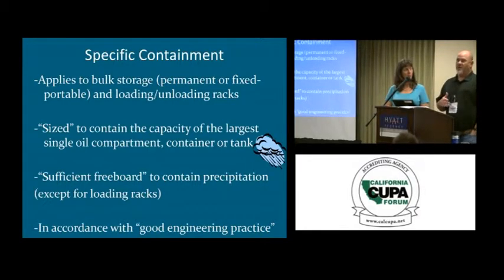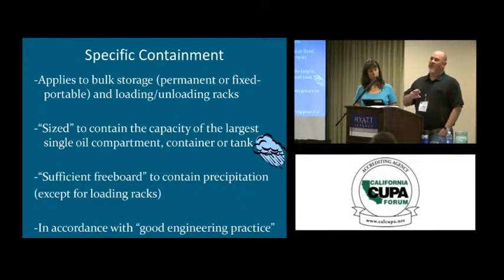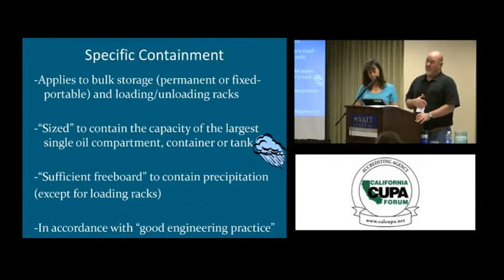So I think what he's getting at is there are requirements for sufficiently impervious containment, and the SPCC rule was modified to remove any language or intent of retaining spilled oil in a containment for 72 hours. That is a little bit too prescriptive for EPA. We rely on the professional engineer for the facility to make the determination as to what is going to be sufficiently impervious. And there's, again, flexibility. If you have a thick crude oil, some sort of compacted earth, basin and dike would be, in my opinion, probably pretty adequate to clean the oil up. So the rule now says sufficiently impervious to contain spilled oil until cleanup can occur. So rather than say 72-hour retention time, we now say till cleanup can occur.